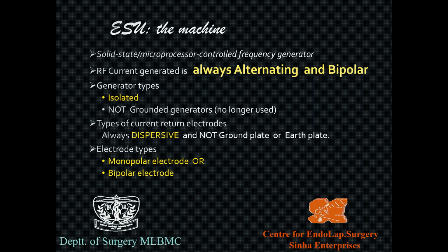Now, the electrosurgical unit, whose specifications we just talked about, is basically a solid state microprocessor controlled frequency generator. And it always generates an alternating, bipolar current. What does bipolar current mean? That means the current leaves the machine from one side and has to come back to the machine from a different side. So it has to have two poles, the positive and the negative.